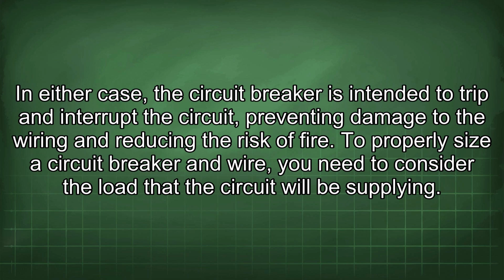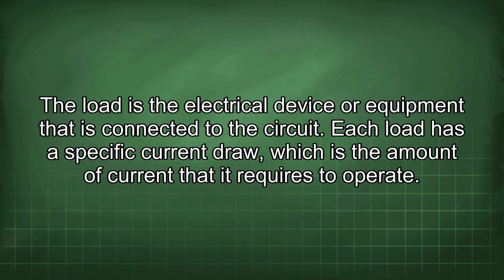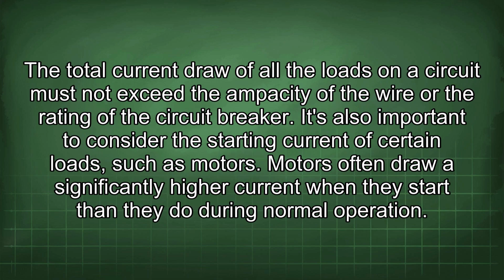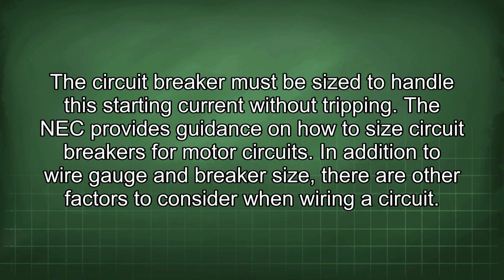To properly size a circuit breaker and wire, you need to consider the load that the circuit will be supplying. The load is the electrical device or equipment that is connected to the circuit. Each load has a specific current draw, which is the amount of current that it requires to operate. The total current draw of all the loads on a circuit must not exceed the ampacity of the wire or the rating of the circuit breaker. It's also important to consider the starting current of certain loads, such as motors. Motors often draw significantly higher current when they start than they do during normal operation. The circuit breaker must be sized to handle this starting current without tripping. The NEC provides guidance on how to size circuit breakers for motor circuits.